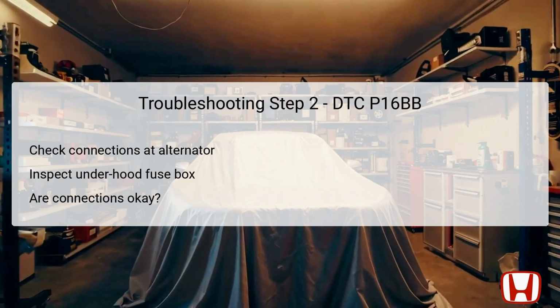If any connections are found to be loose or corroded, they should be repaired or replaced as necessary. After addressing any issues identified during this inspection, perform a repair verification to confirm that the circuit functions properly. This step is essential to establish a reliable foundation before moving forward in troubleshooting the electrical system.